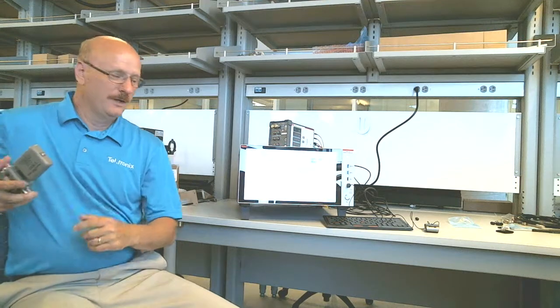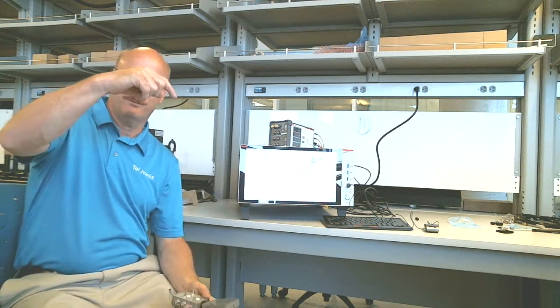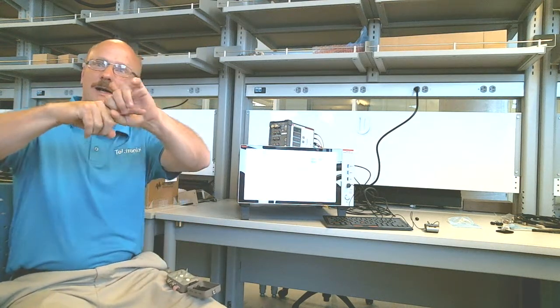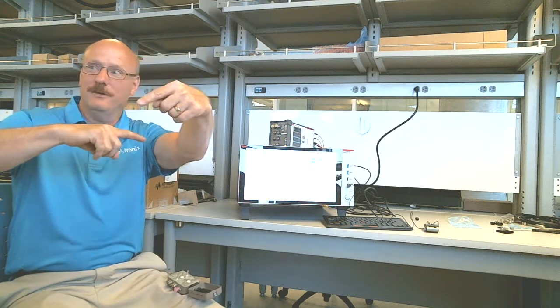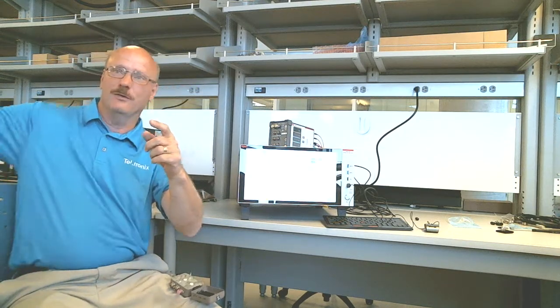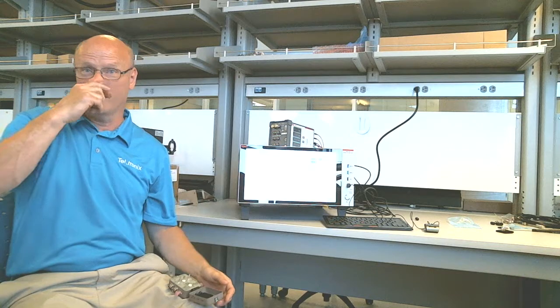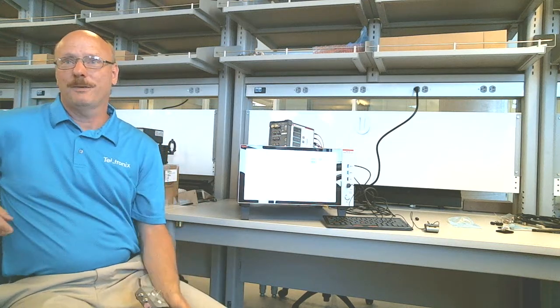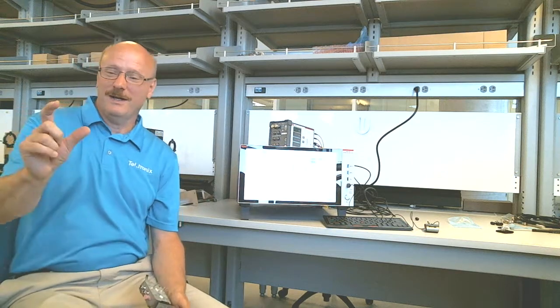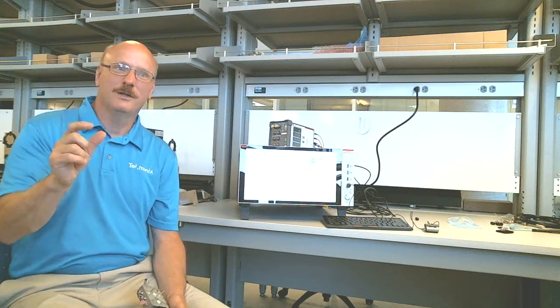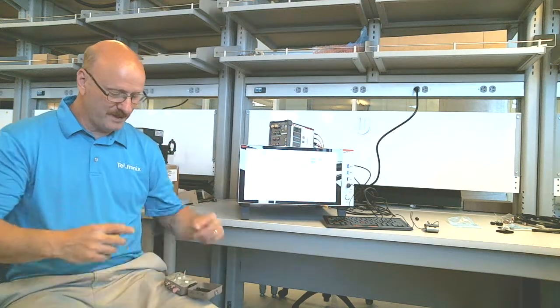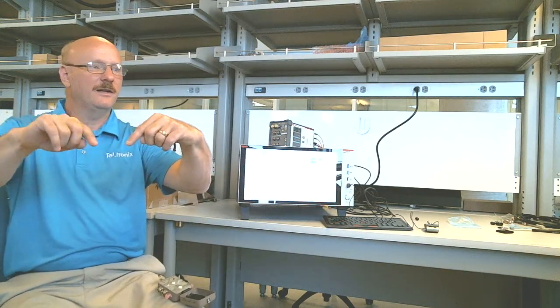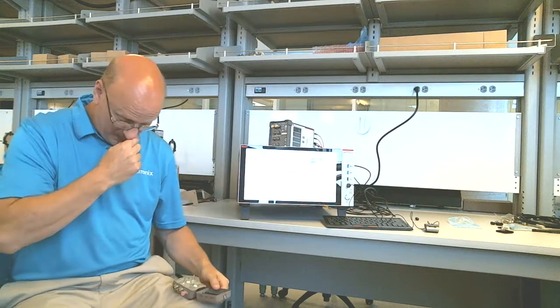So you have your probe, your center conductor, then there's the outer shield around it. Those need to be tied together. Otherwise you have a big inductive loop that makes it very difficult to make good capacitance measurements. You have to keep that as short as possible, and as close to your device as possible. So you bring your probes in and jumper them right there, as close to your probe as you can.